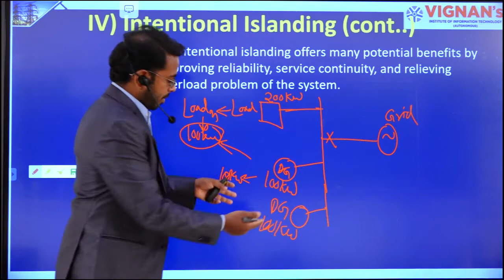So what will we do? We can schedule the load according to how much is available. For us, 100 kilowatt is available, so we can reduce the new load to 100 kilowatt. So how much power is available, that we can give. So service continuity we can give, or you can add one more DG of 100 kilowatt capacity.